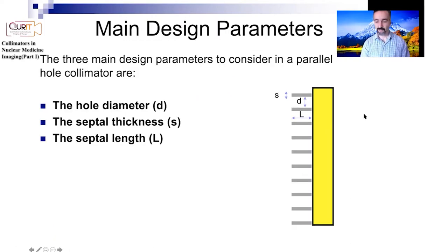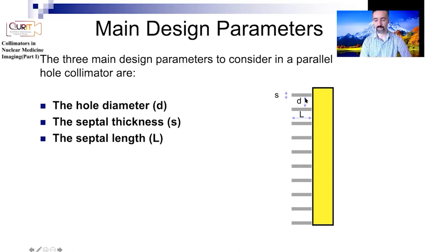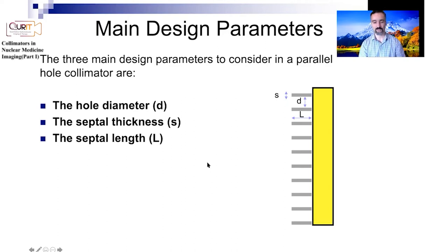The right collimator is contextual — it depends on the application. For a parallel hole collimator, there are three main design parameters to consider: the hole diameter d, the septal thickness s, and the septal length l, which is the height of the collimator.